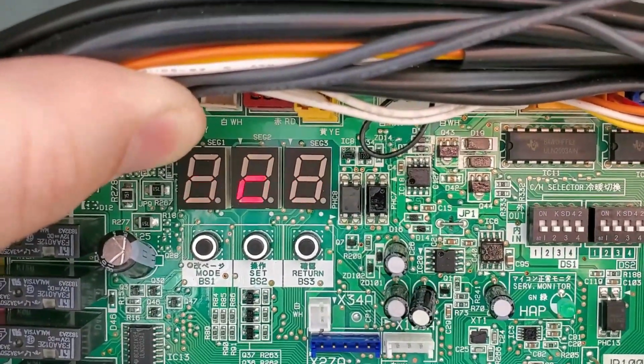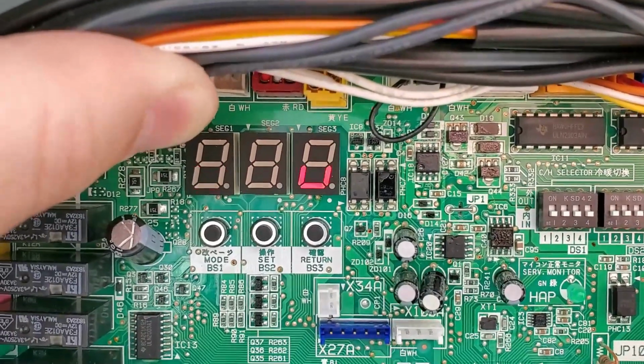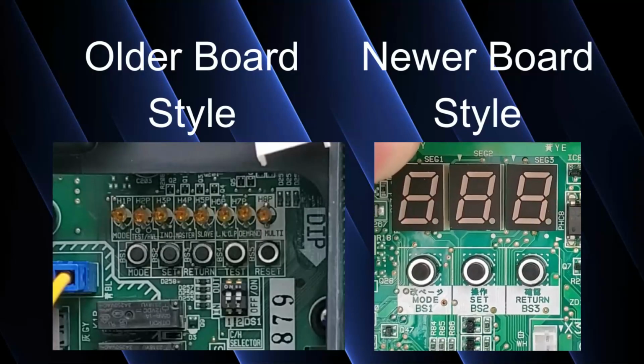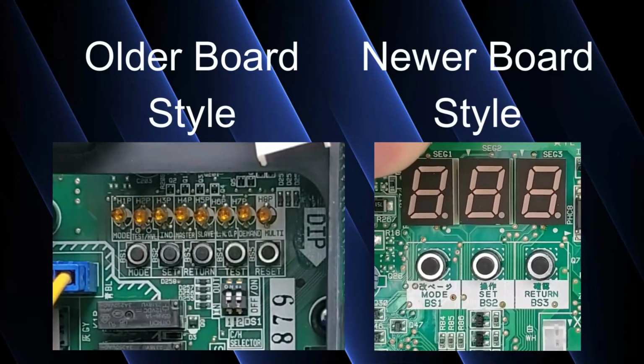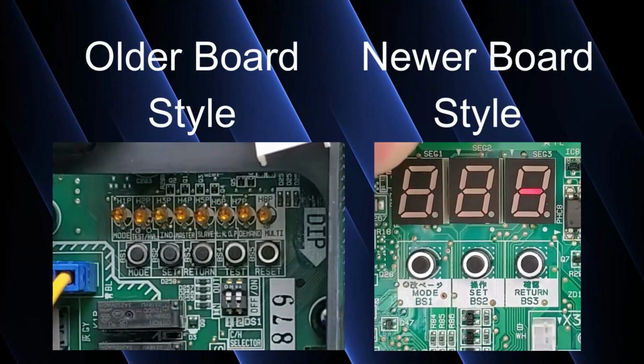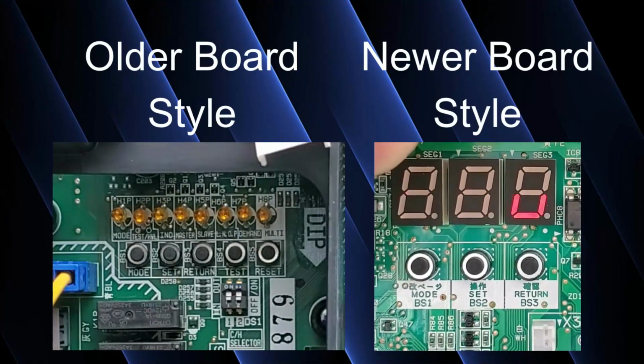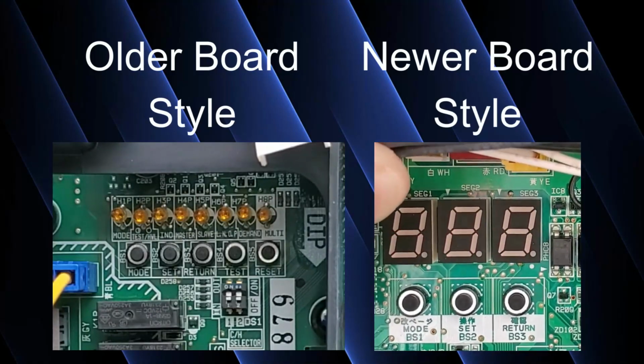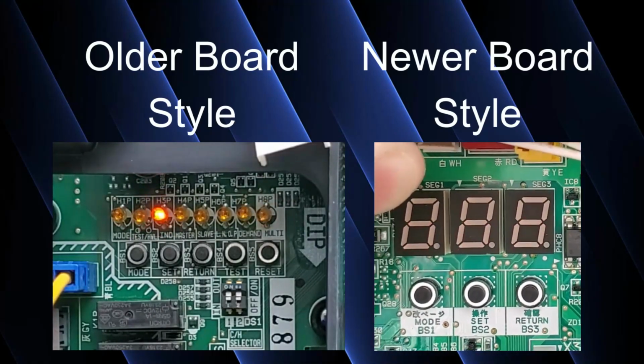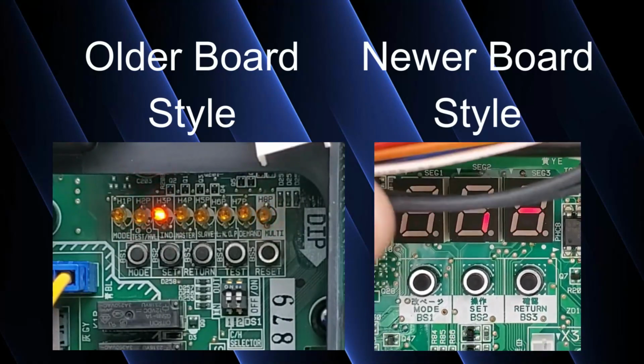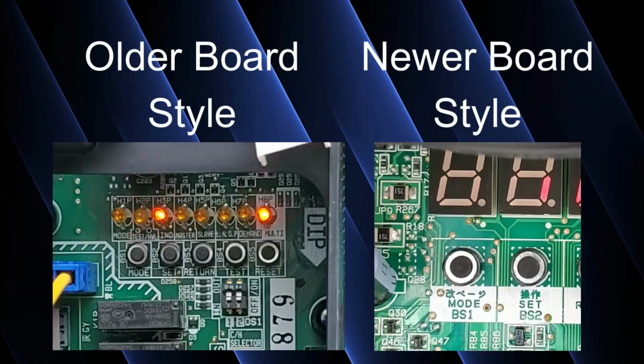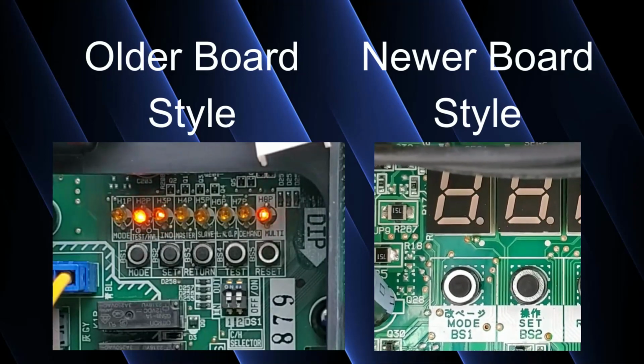But basically, you're going to sit there and wait for the outdoor unit to go to a blank screen on VRV4 generation systems and later. These are the systems with the newer PCBs. If you have an older unit, say you have a VRV3 or a VRV2 or even a single phase VRVS or a VRV Life, or maybe you have one of those hybrid RMXS 48s. They're like a VRVS outdoor unit, but they have a different port box. It's a manifold with valves. It's like mini splits on the indoor side and VRV on the outdoor side. Anyways, it's a hybrid. It's super old. We never sell them anymore, but I digress.